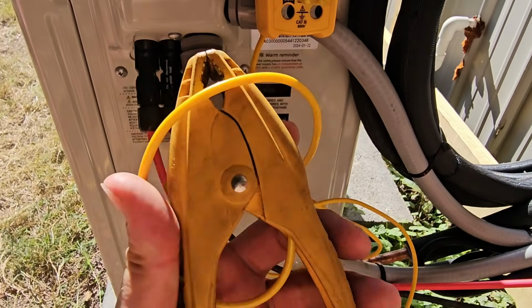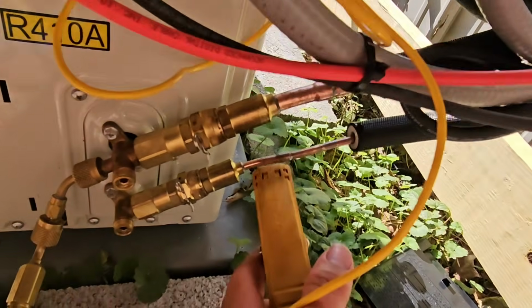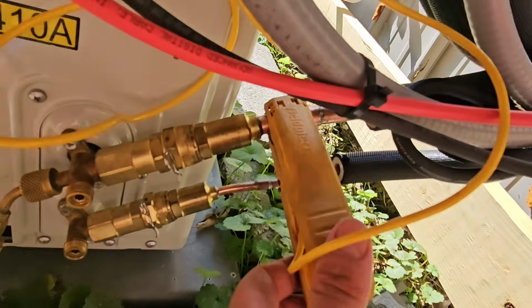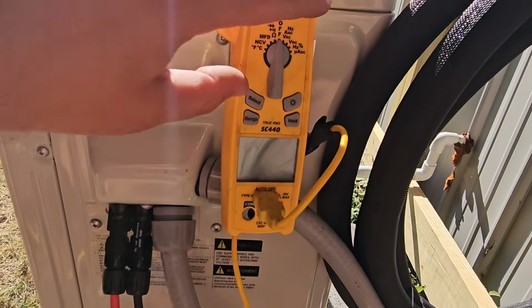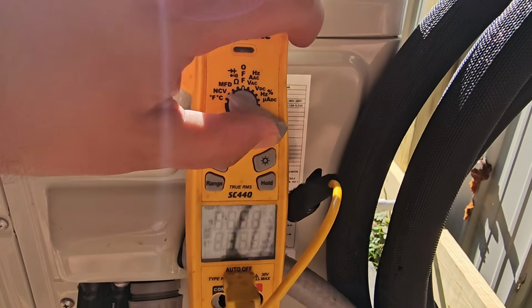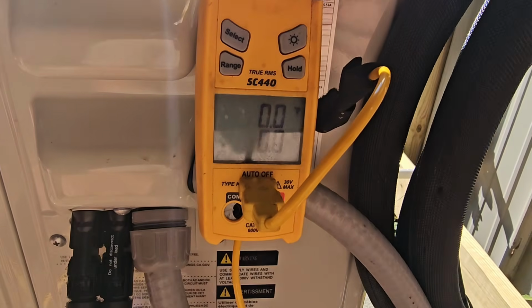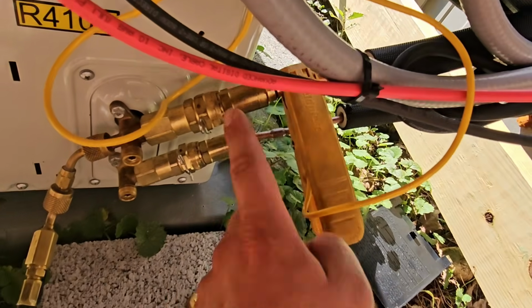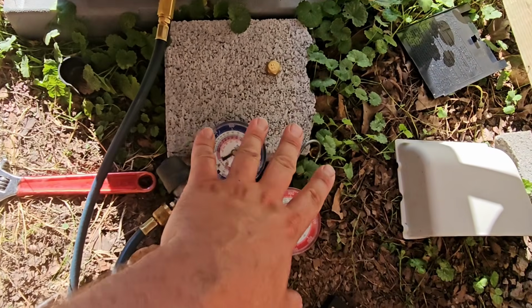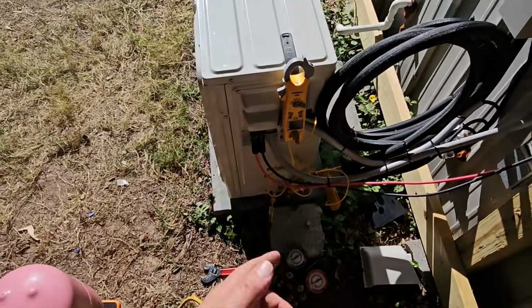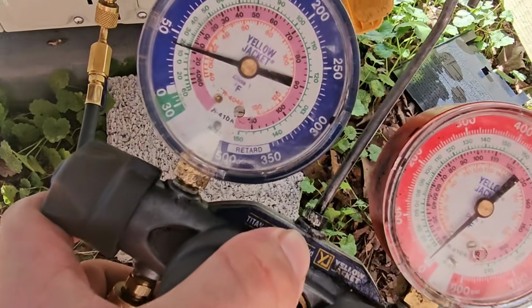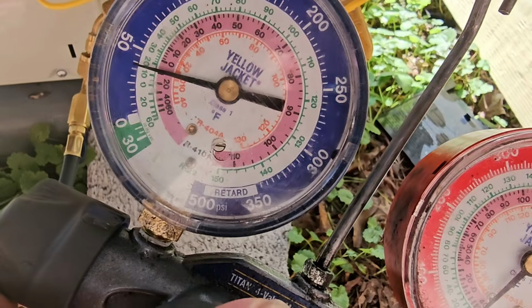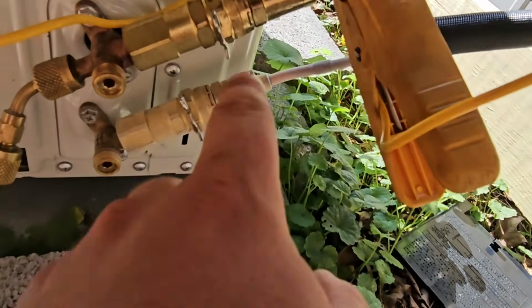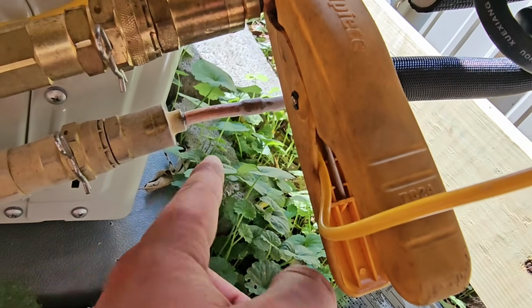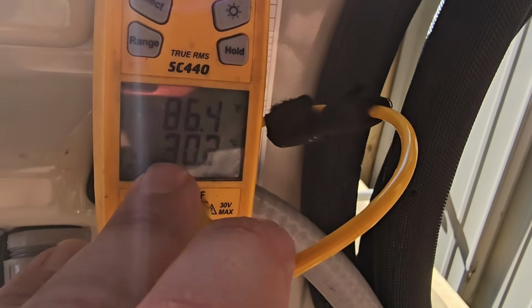I've got my temperature clamp connected to my gas pipe, the suction pipe. I've got that clamp connected to my meter, and I'm going to turn the dial to Fahrenheit. And we're going to measure the temperature of this line right here, and we're going to measure the pressure and the supply air temperature. So it's been running a few minutes. Low side pressure is like 40. It's going down more. The liquid line is freezing. You can see it freezing up. The suction line temperature is 86.